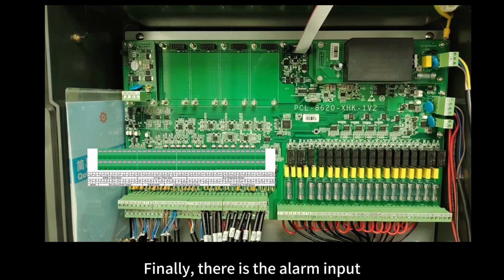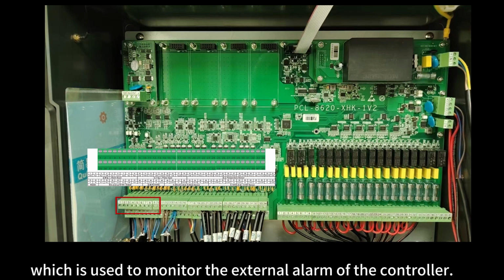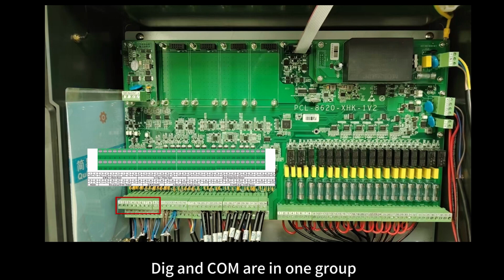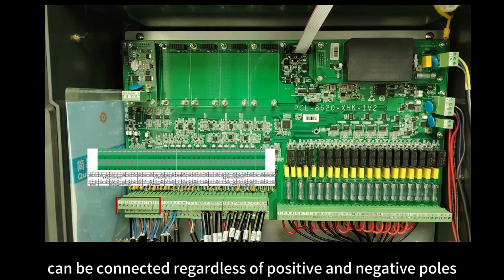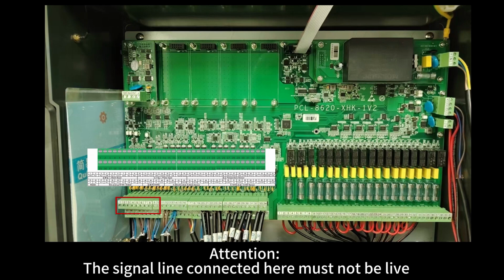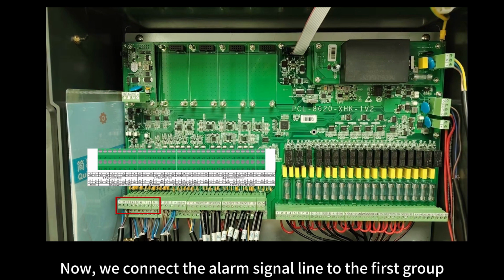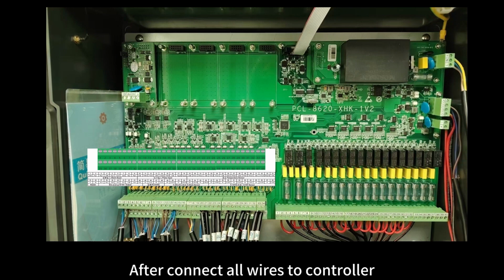Finally, there is the alarm input, which is used to monitor the external alarm of the controller. Total are 6 groups. DIG and COM are in 1 group, can be connected regardless of positive and negative poles. Attention! The signal line connected here must not be live. Now, we connect the alarm signal line to the first group. After connecting all wires to the controller, the user can power it.